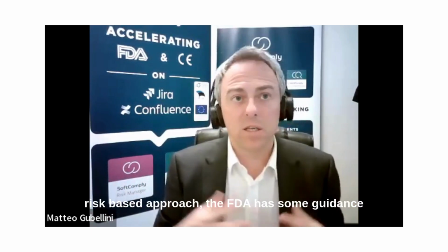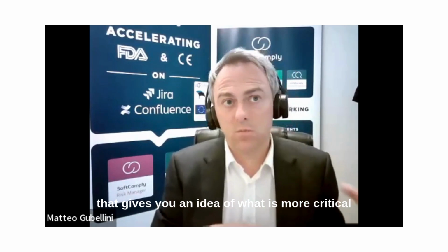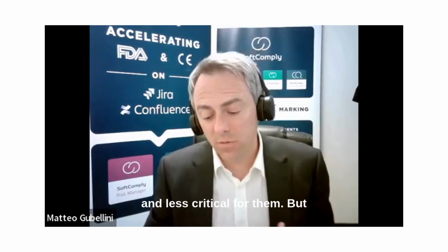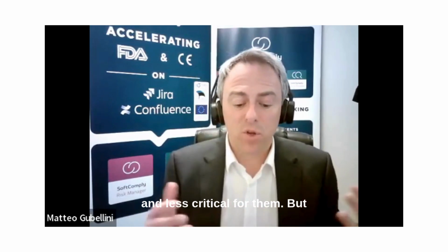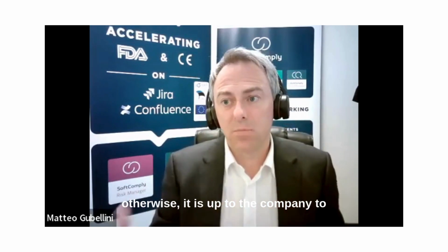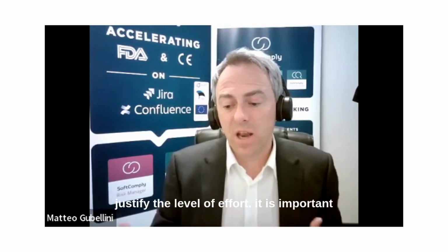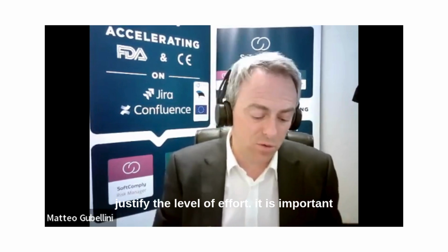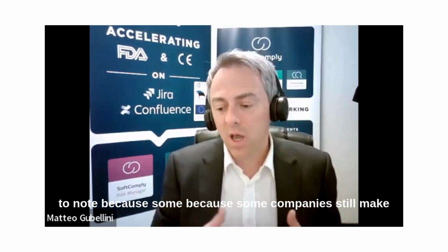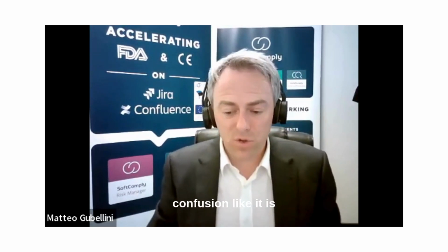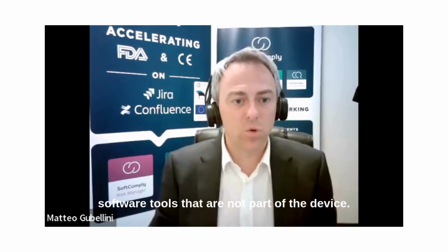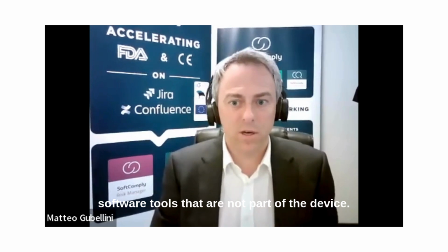The FDA has some guidance that gives you an idea of what is more critical and less critical for them. But otherwise, it is up to the company to justify the level of effort. And it is important to note, because some companies still get confused, that these are software tools that are not part of the device.